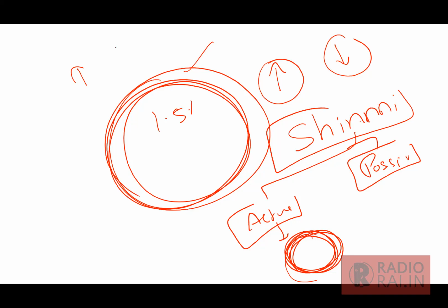If I put it in the reverse direction, it will reduce. This is active shimming. Passive shimming is when we keep some metal pieces within the magnetic field. This is done when the MRI gantry is produced. Some metal pieces are kept inside the gantry, which will induce a magnetic field and help in changing the magnetic field in the places where it is required.